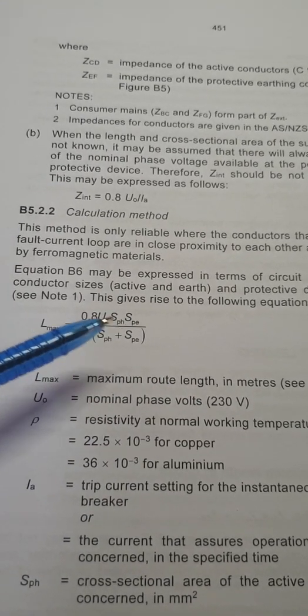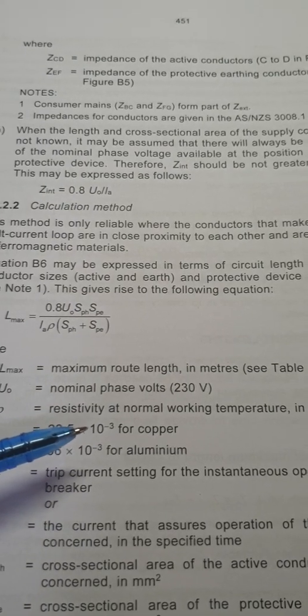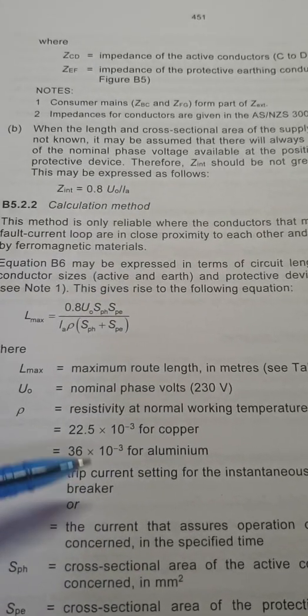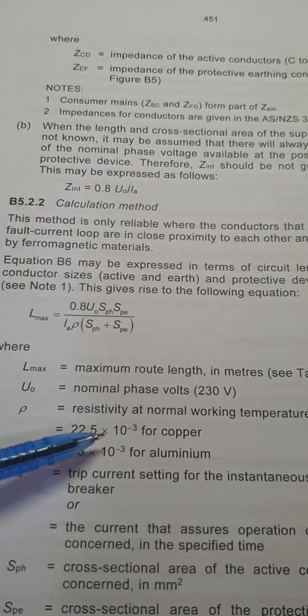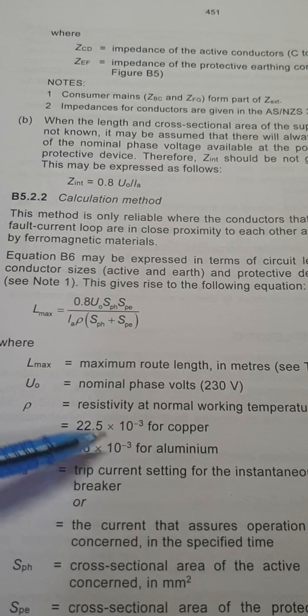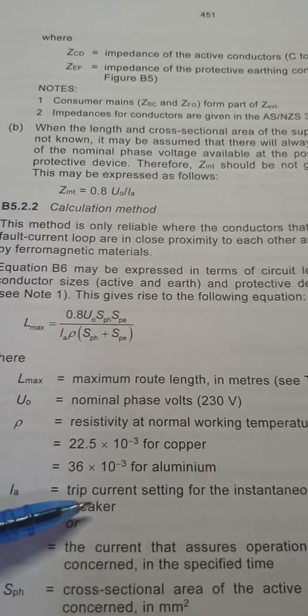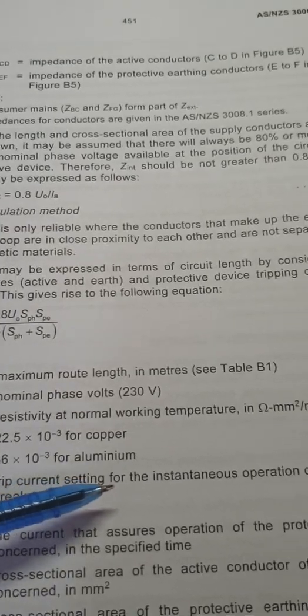L max is for the maximum length. That's what we're working out. Then we have nominal voltage is 230 volts. That's under the V here. Then resistivity of the working temperature in the cables per meter, so 0.225 worked out to be 22.5 times 10^-3, same with the 36. So that's for our P.